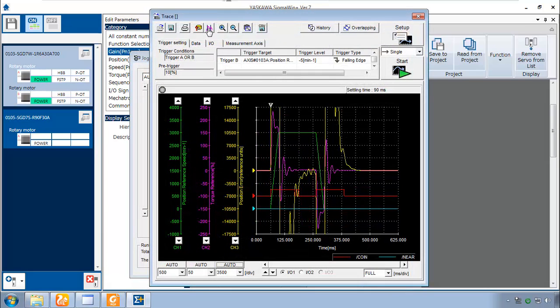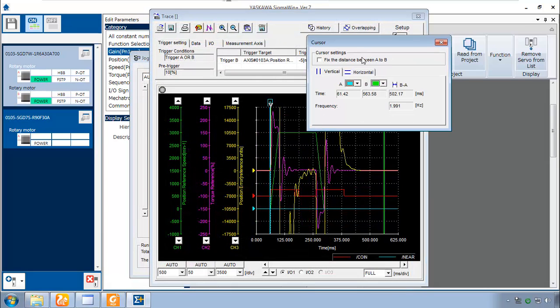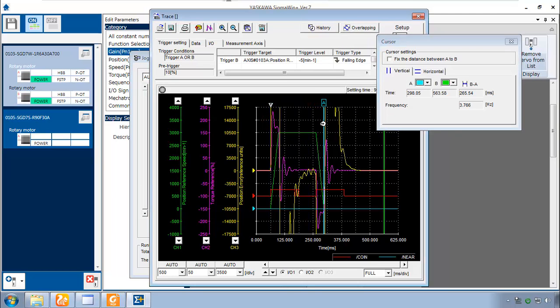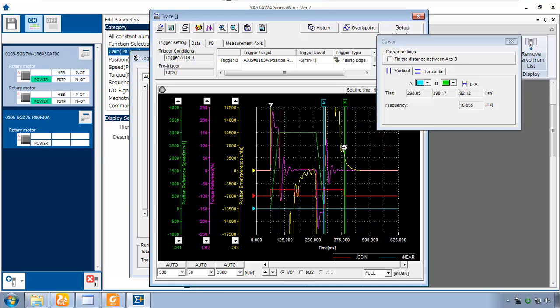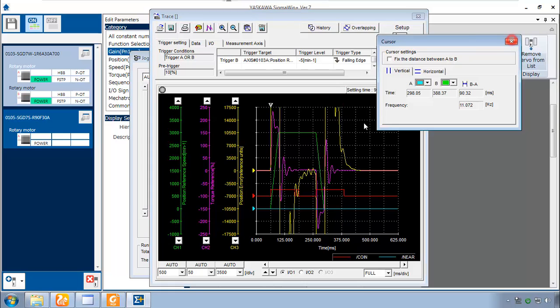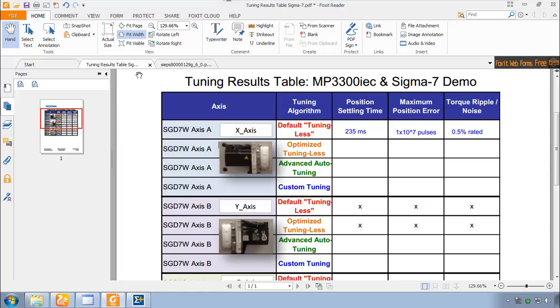So let me just confirm here this automatically measured settling time is. There's the end of the move. There's the coin signal. 90 milliseconds. And that's what we have here for the auto measurement. 90 milliseconds. I'm going to write that in here for our optimized Tuningless position settling time. Got it down to 90 milliseconds.